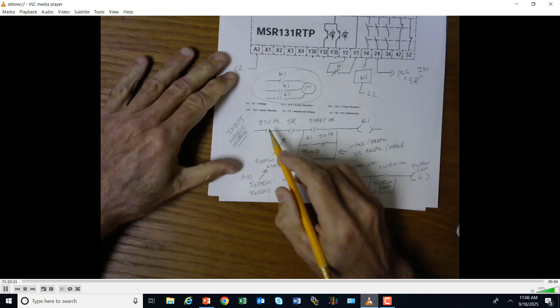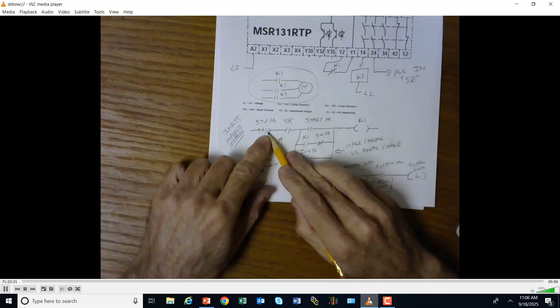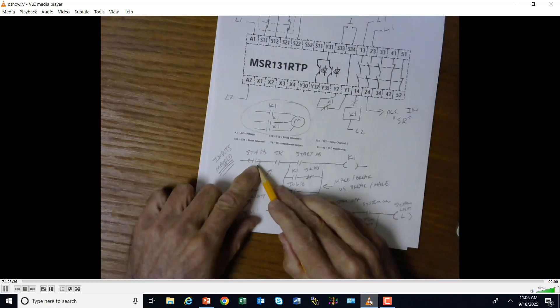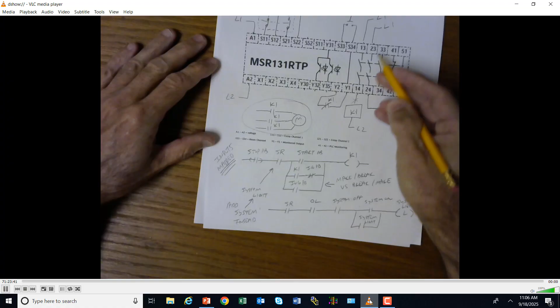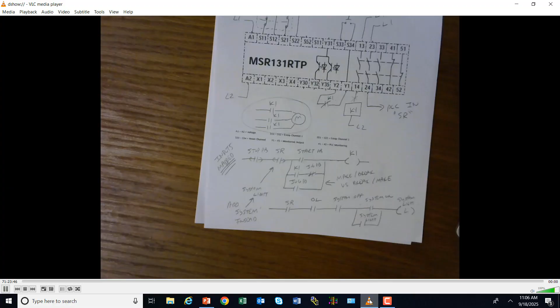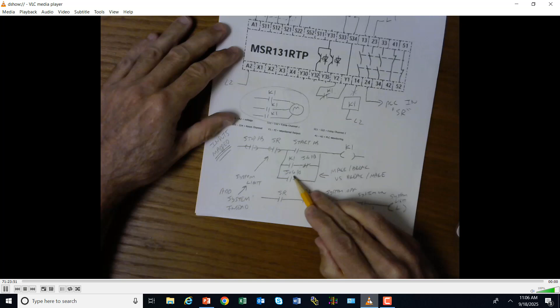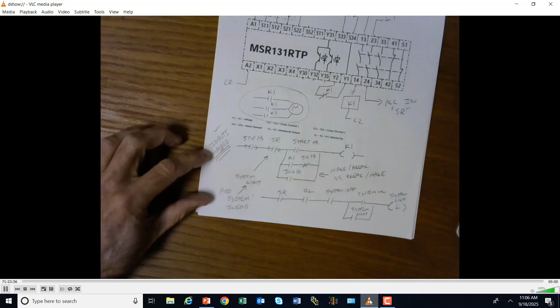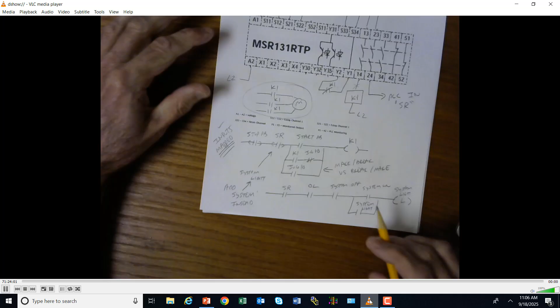We had a stop button that would have been a normally closed. Remember, this is not the E-stop. It's just a normally closed stop. If I hit the stop button, that in no way affects the safety relay. That's just the stop for the program. And then I had the start button. That's the safety relay contact we needed, when the safety relay's reset, well, then that's going to close. And then I just did my memory here, and I had my jog button here, opening and closing. Remember the make-break versus break-make. Input mapping becoming critical for this to work like we want it to work, right?